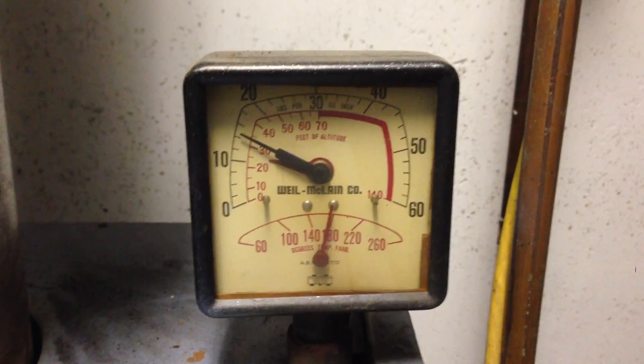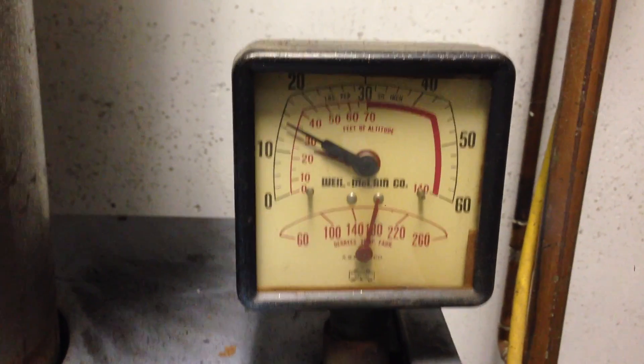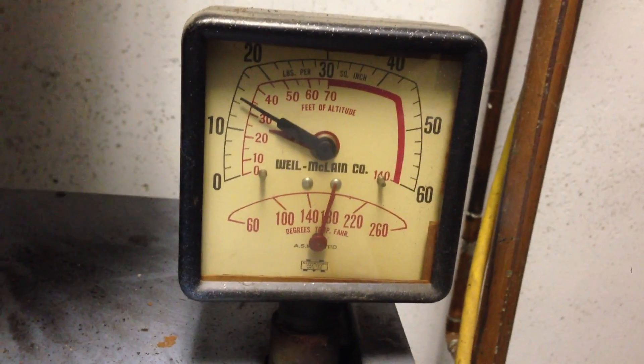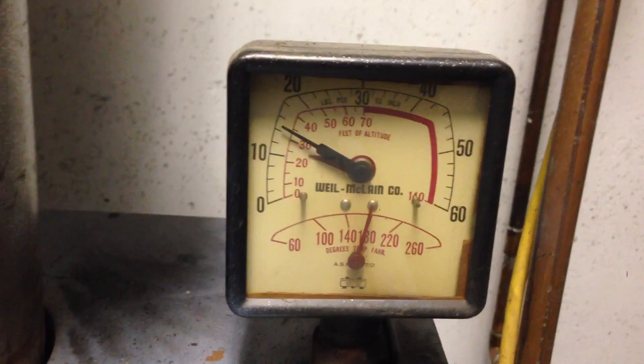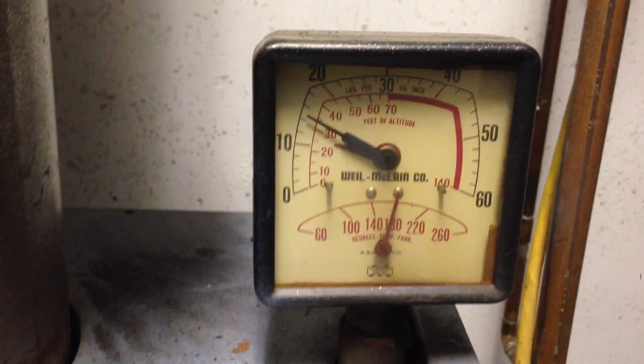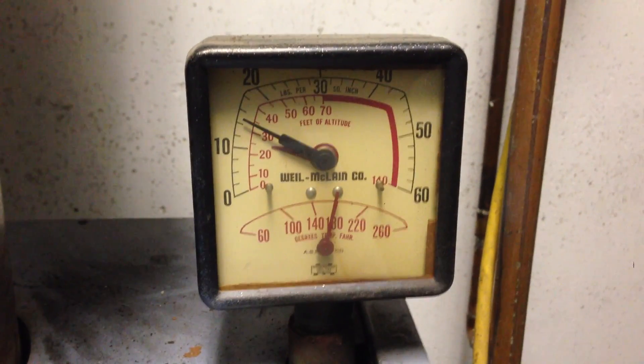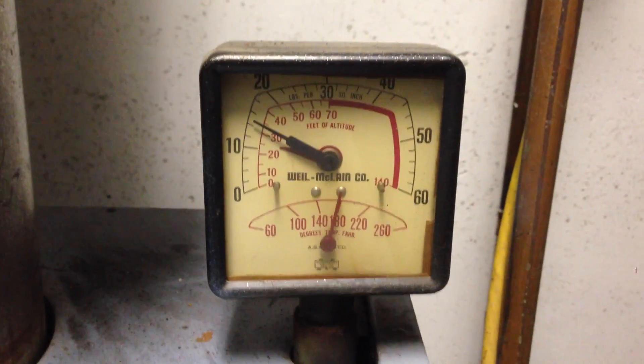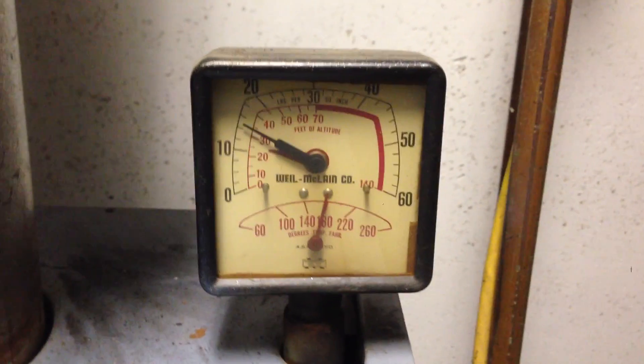I've been monitoring this for about 40 minutes, coming down every 15 minutes or so and checking it. It's looking pretty good, pretty stable. I'm not seeing the pressure or the temperature get up to anything too ridiculous, so it looks good. I could probably even turn it up another 10 degrees if I need to. It's minus 15 right now — maybe down to minus 20 or 25, who knows. We just have to bundle up a little bit. I'm not sure I want to stress a furnace this old any more than I have to.